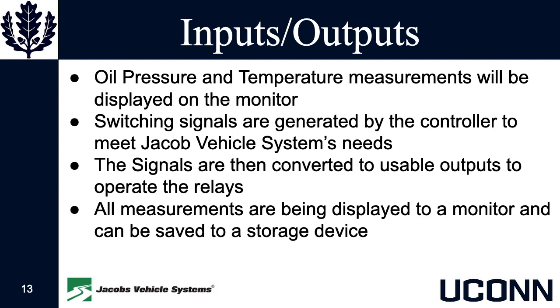So our inputs and outputs going into and out of this controller are mostly going to be temperature and pressure transducers that the Rio is going to be getting from our oil supply to each of the solenoids, and the outputs are mostly going to be our switching signals that are going to be generated by the Rio, and those are going to be controlling the solenoids that are inside this test bench.